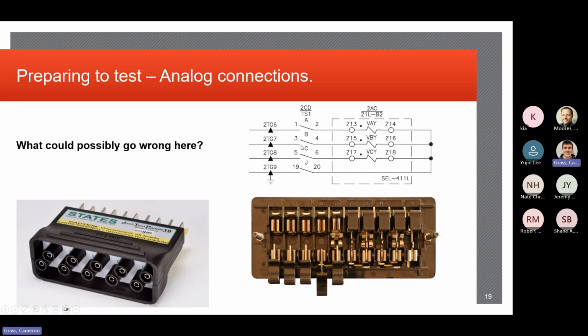And this is kind of one of the big things. Can anybody tell me what would be an issue based on specifically the test switch on the schematic in the top right and how the test switch is configured on the bottom right? We talked about it last week where we had these paddles that we basically just throw right into the knife switches so that they directly supply currents and voltages straight up to the relay. Well, if you were to do that in this situation based on the schematic, and if it was physically wired per the schematic, what would happen?